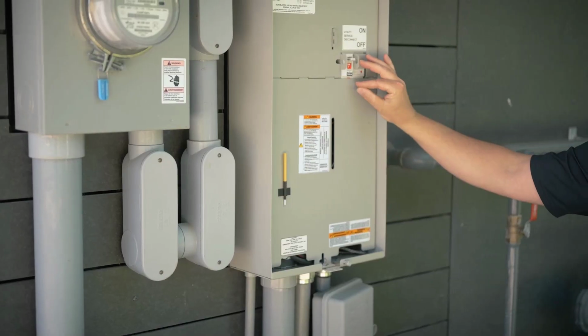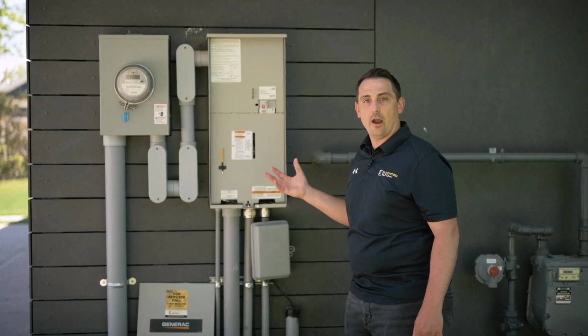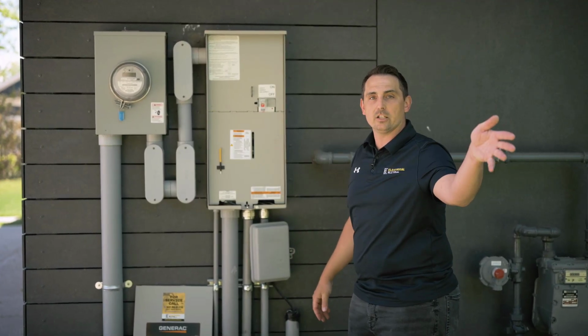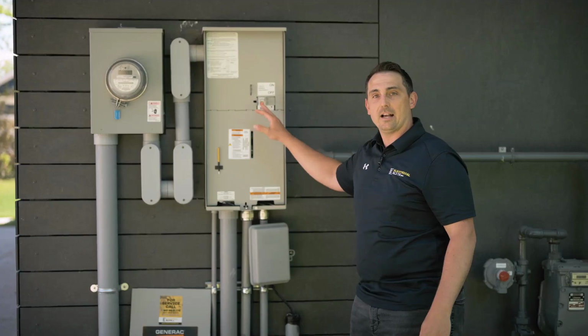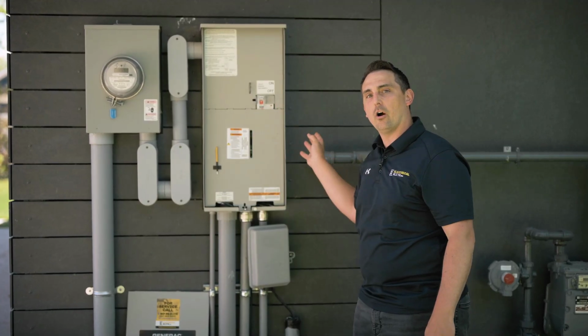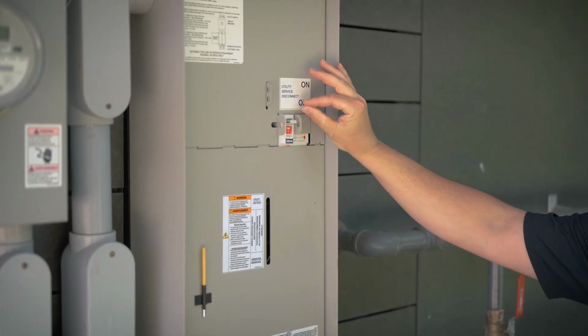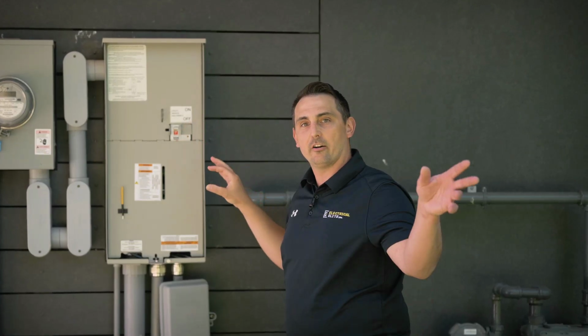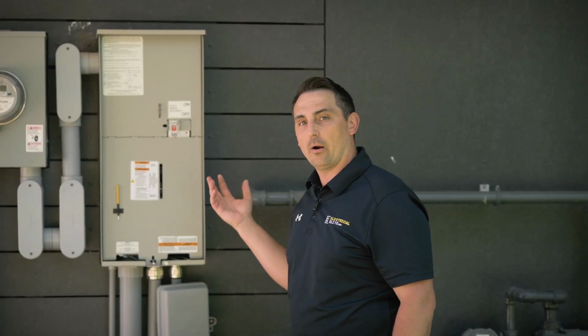Turn it to the off position. It'll sense that the power has gone out. The generator will automatically start, and the ATS will transfer the generator power to your home. When you're satisfied with the test, you can go ahead and turn this breaker back to the on position. The ATS and generator will sense that the power's been restored and transfer back to utility power. Again, the generator will automatically turn off.